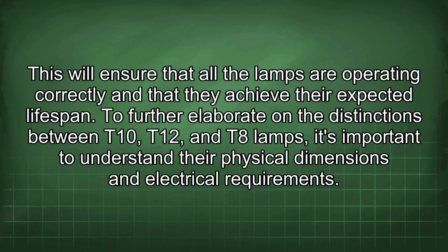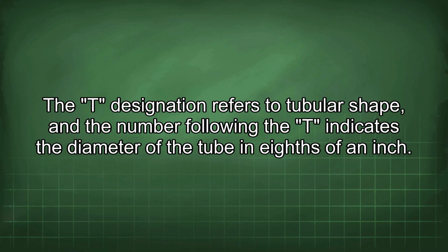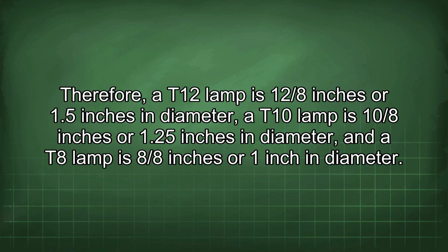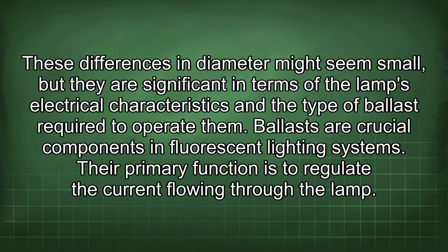To further elaborate on the distinctions between T10, T12, and T8 lamps, it's important to understand their physical dimensions and electrical requirements. The T designation refers to tubular shape, and the number following the T indicates the diameter of the tube in eighths of an inch. Therefore, a T12 lamp is 12/8 inches or 1.5 inches in diameter, a T10 lamp is 10/8 inches or 1.25 inches in diameter, and a T8 lamp is 8/8 inches or 1 inch in diameter. These differences in diameter might seem small, but they are significant in terms of the lamp's electrical characteristics and the type of ballast required to operate them.